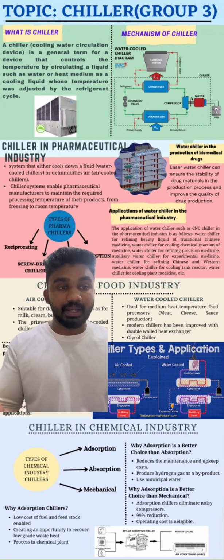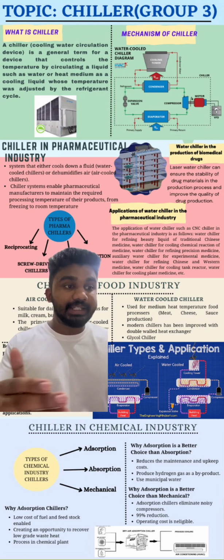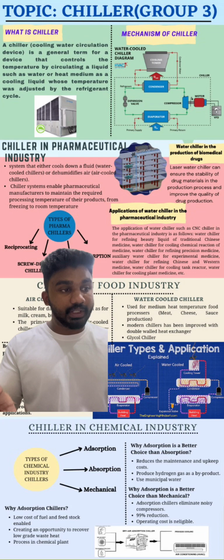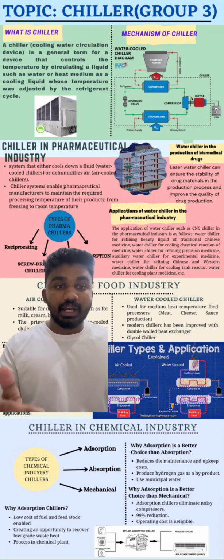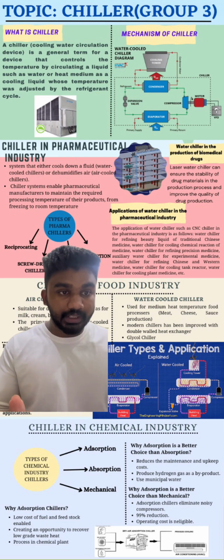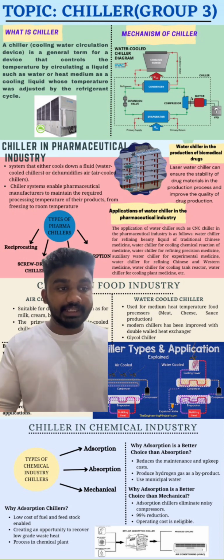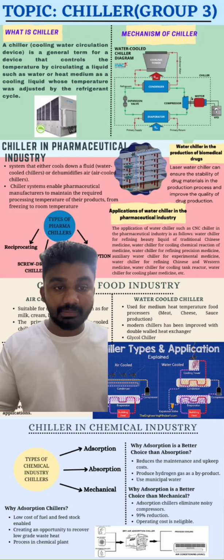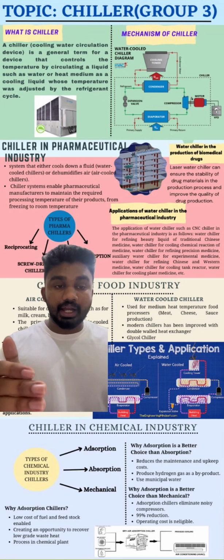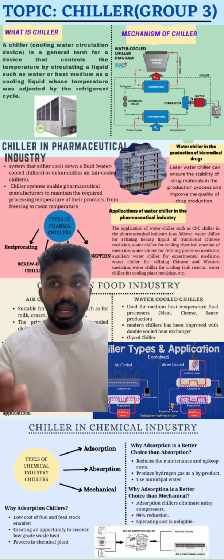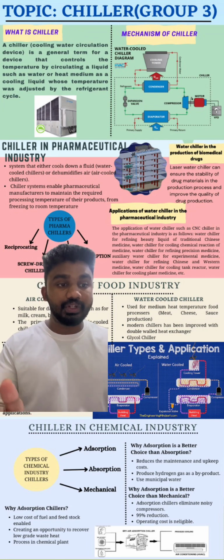Processes in chemical plants like reflux condensers, condensate streams, product coolers, boiler exhausts, boiler blowdown, PRDS cooling, compressor interstage and aftercoolers, and also process furnaces all produce heat that can be used in adsorption chillers to produce chilled water.